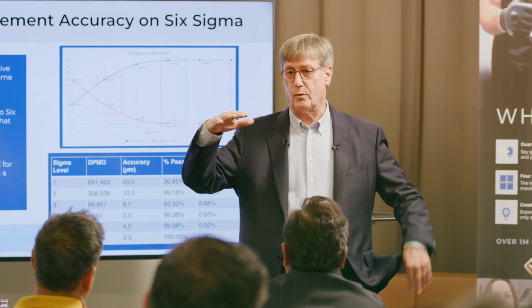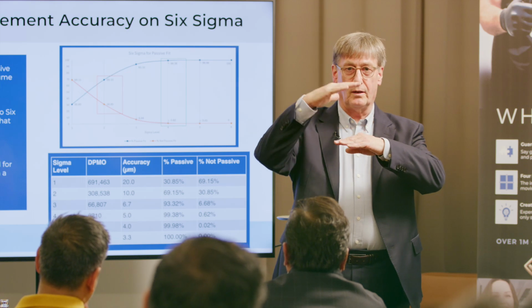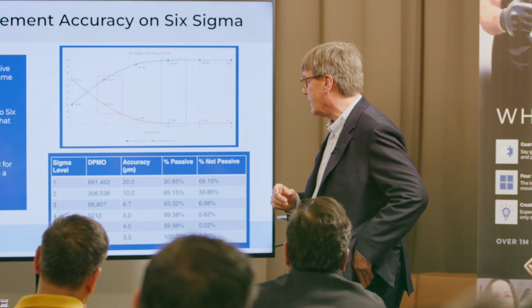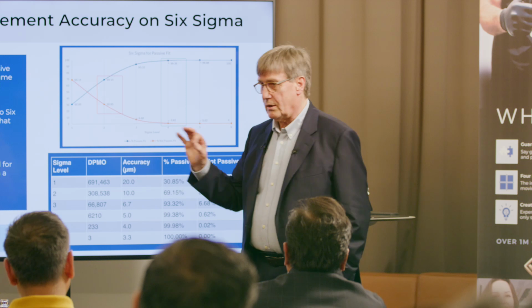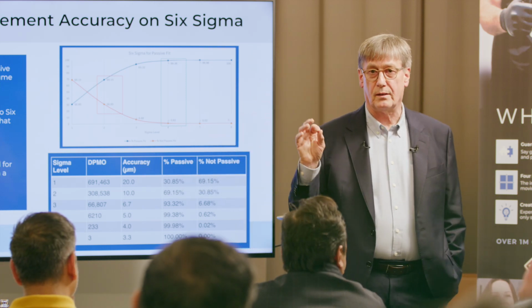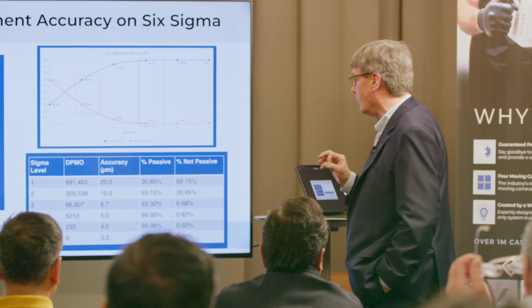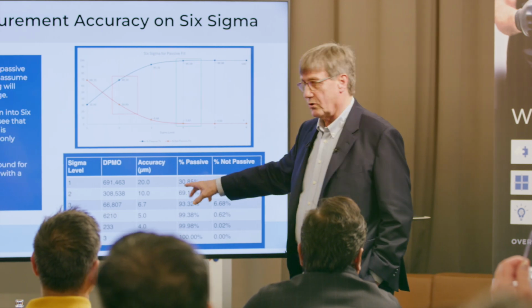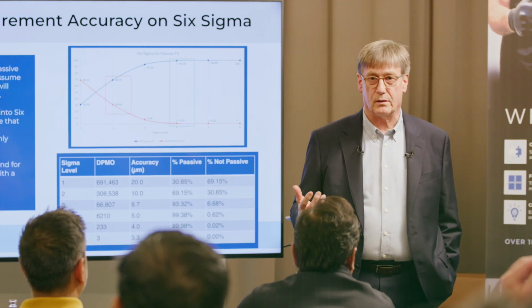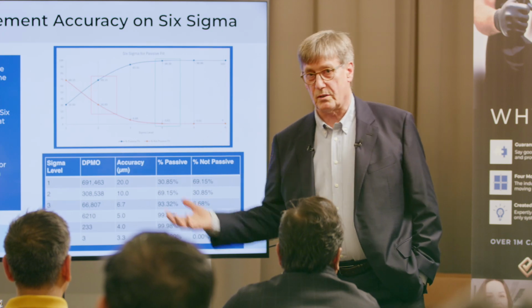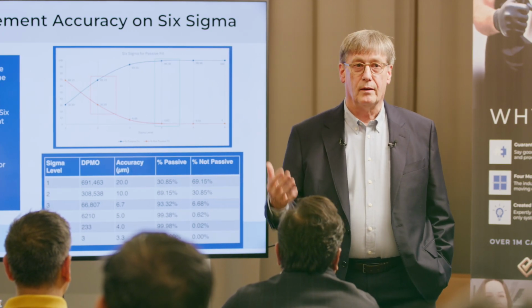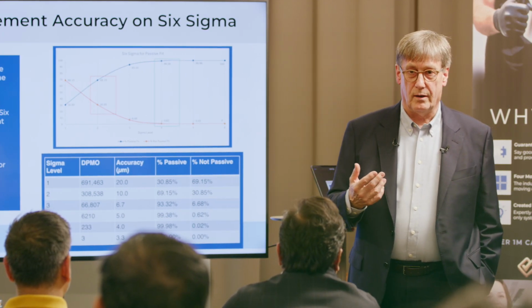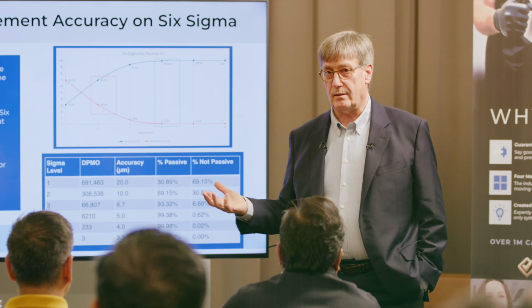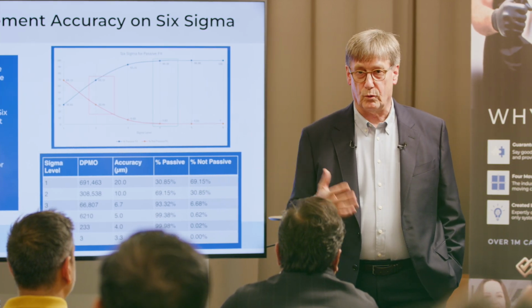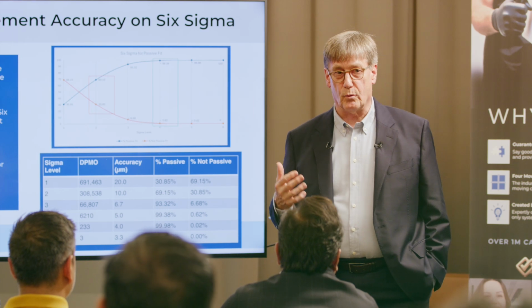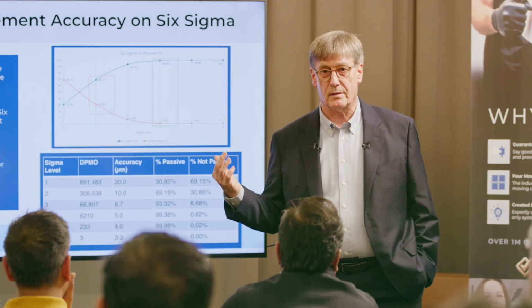And that comes from the point that if you have something on the model that gets bigger than 20 micron, you will see it. Now, if your machine has an accuracy, and that's always standard deviation, our terminology, of 20 micron, you will actually get 30% of your structures that will fit. So even with the worst system, you can be lucky, and it will fit. It's just like if you go over a red light, it's not necessary that you will be dead, but I don't think you will recommend anybody to go over red lights.